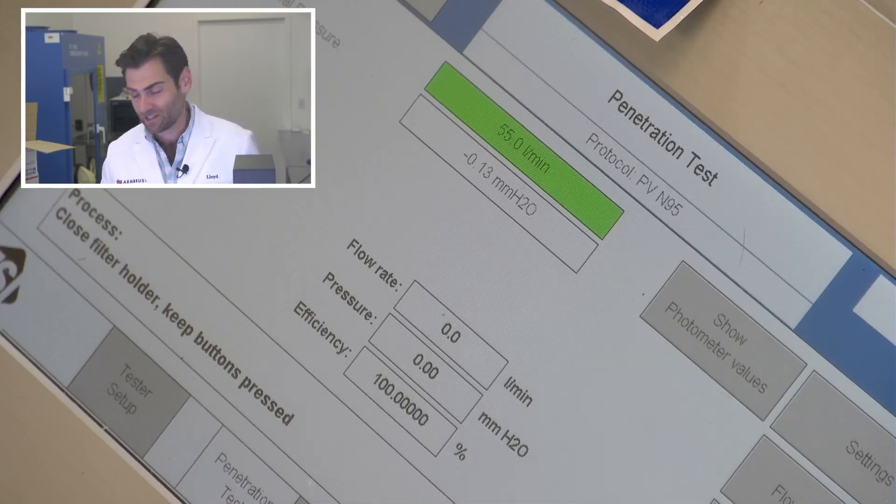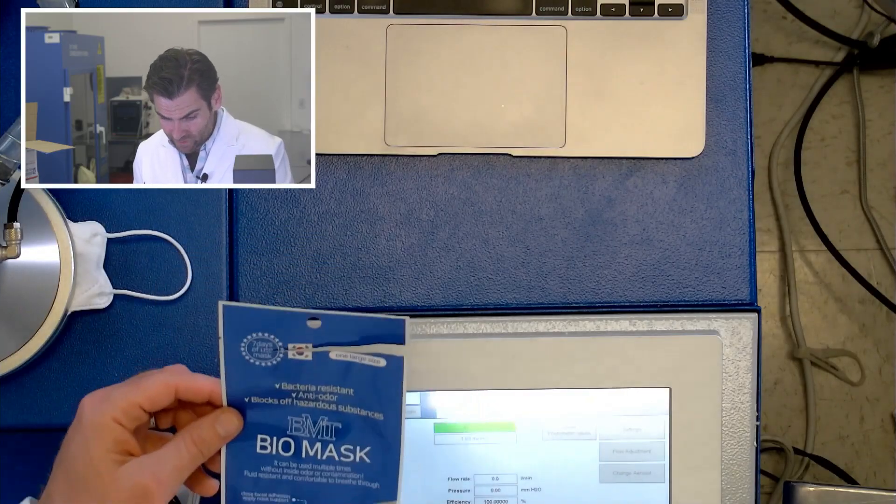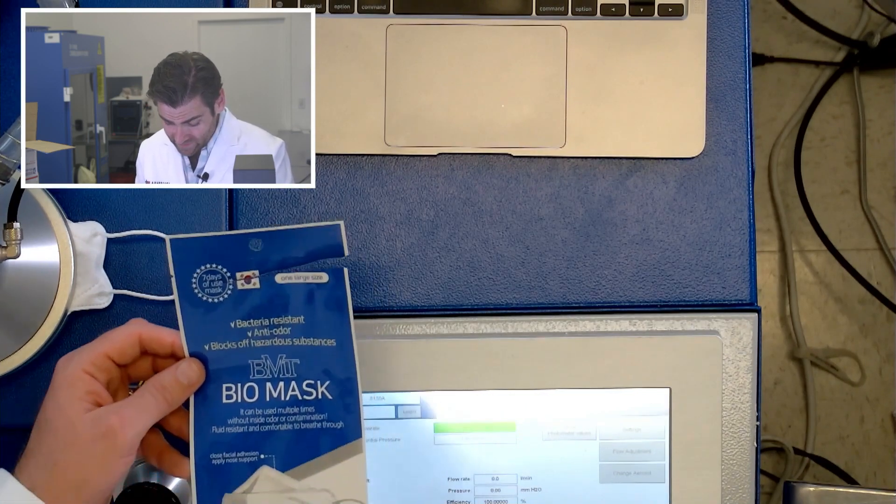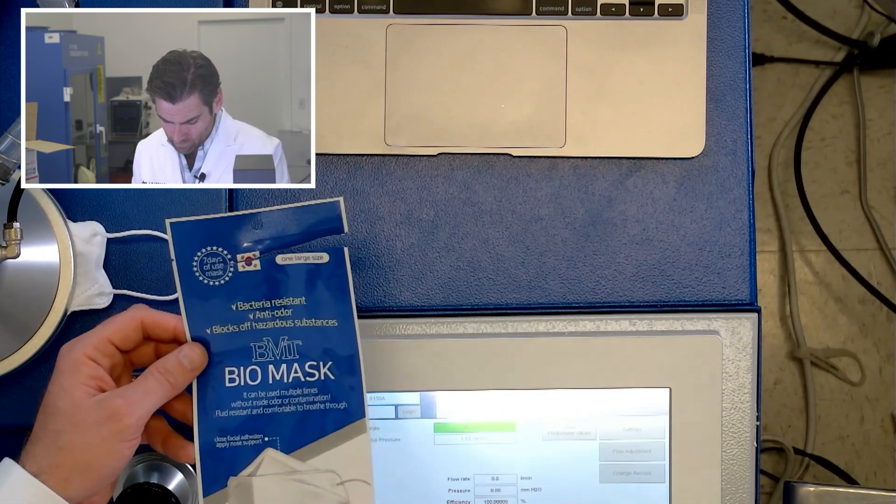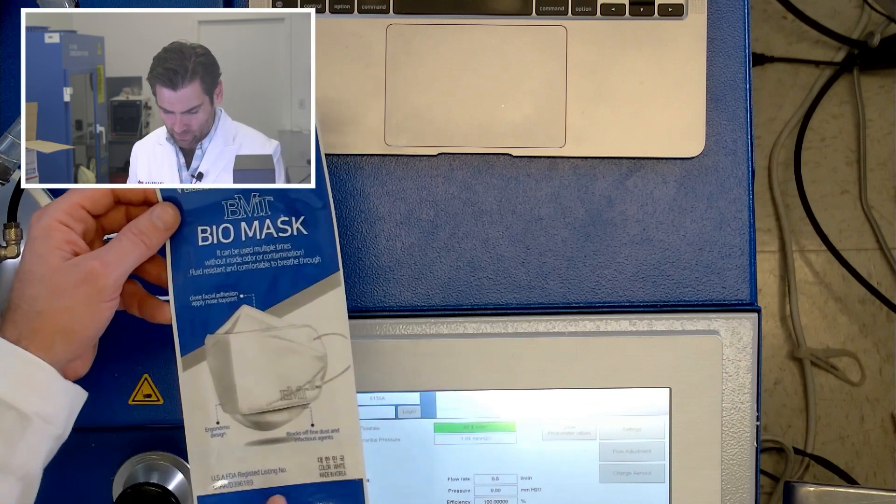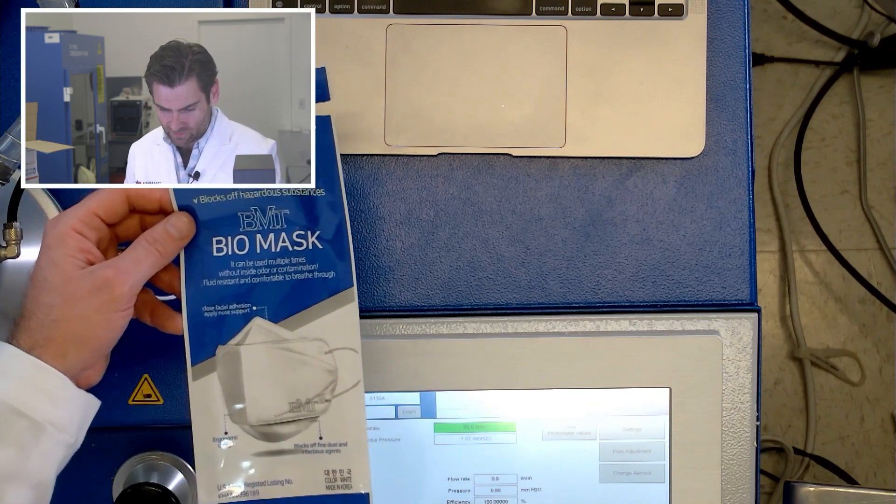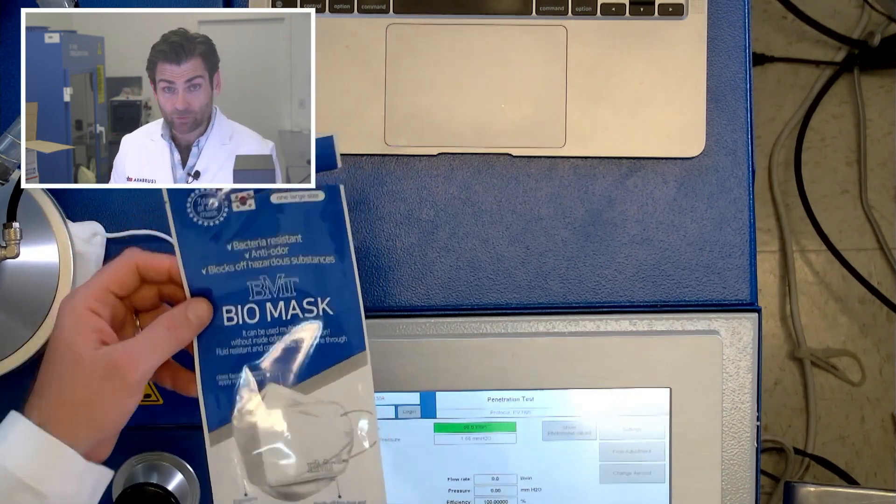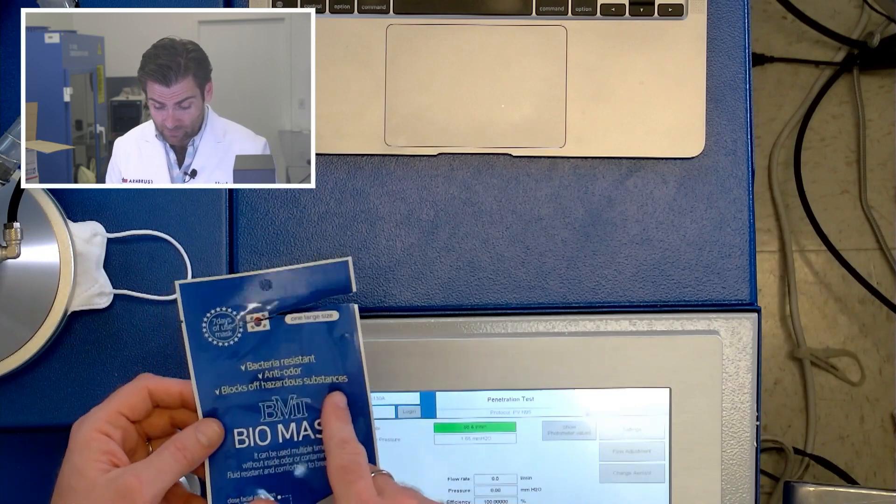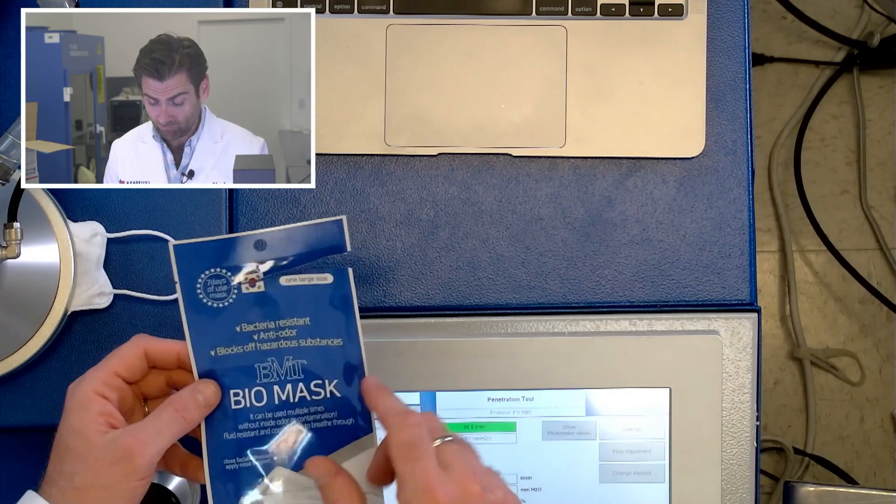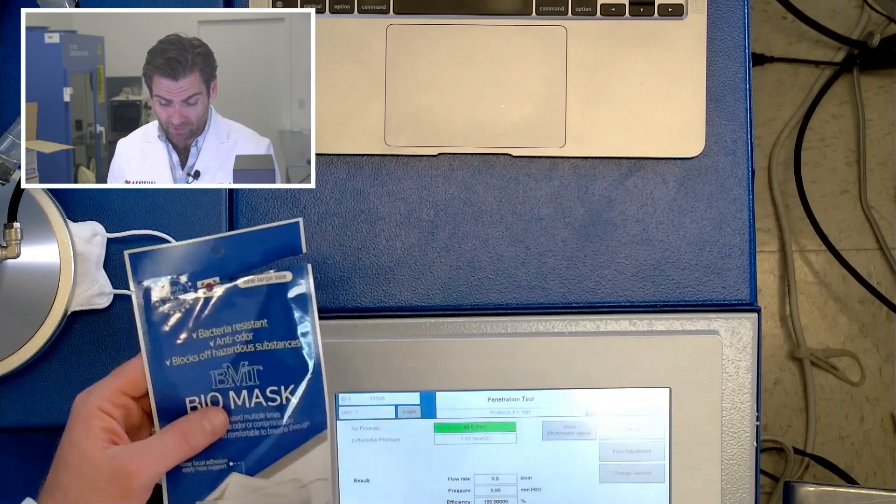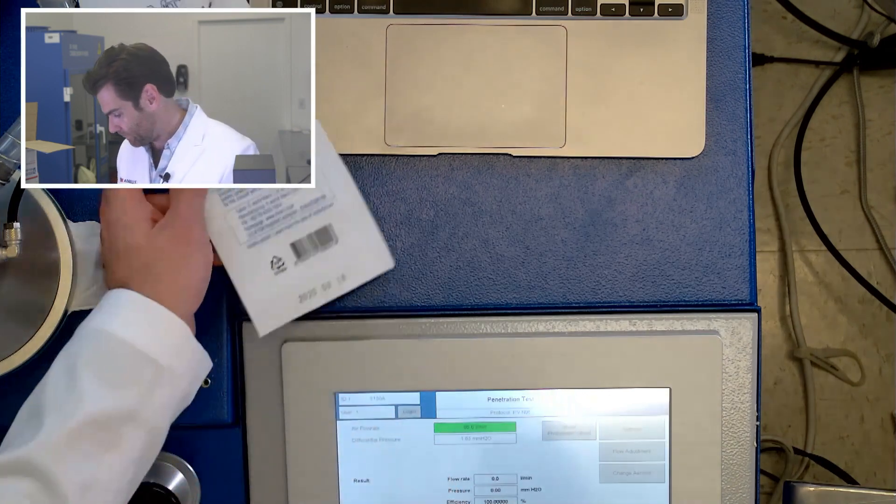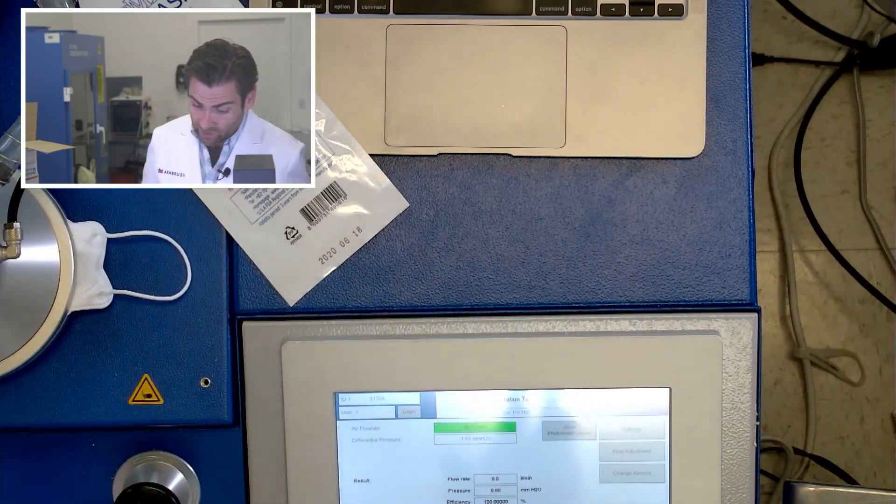This is PFE machine, Particulate Filtration Efficiency machine. It looks like a KF-94, it says seven days of use. It says FDA registered listing, which isn't, that's not a thing for masks, so that's kind of a red flag. US FDA registered listing - manufacturers can be registered but not masks. Although it does block off hazardous substances, I think the FDA would not allow them to say bacteria resistant. I don't know, this seems fake to me. We'll see what happens here.